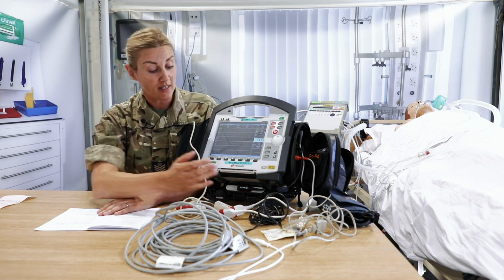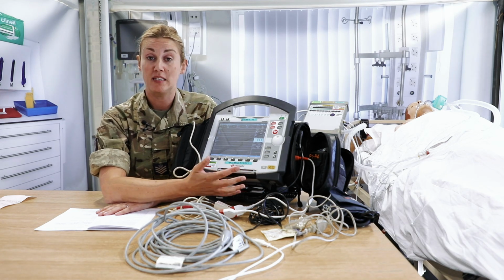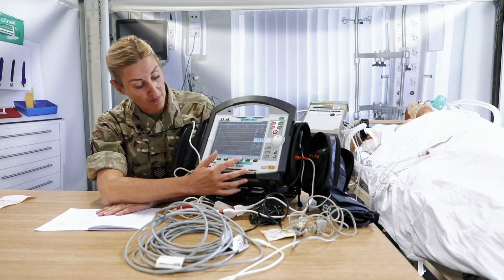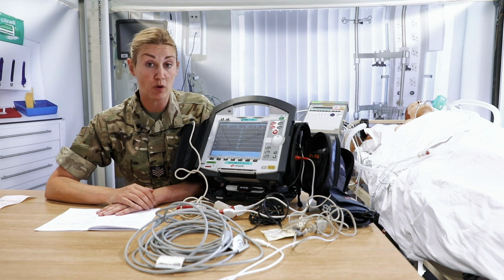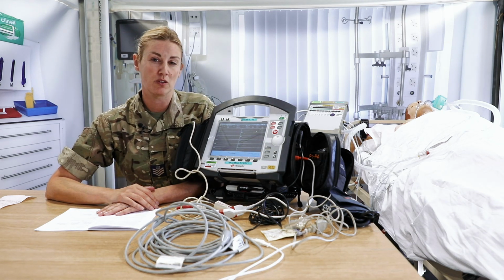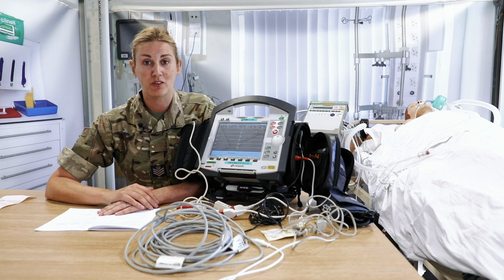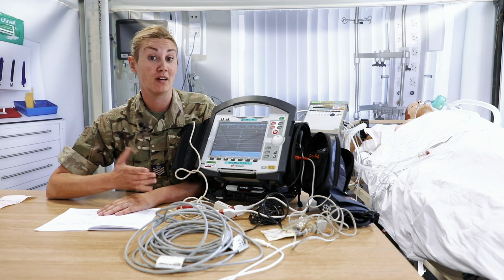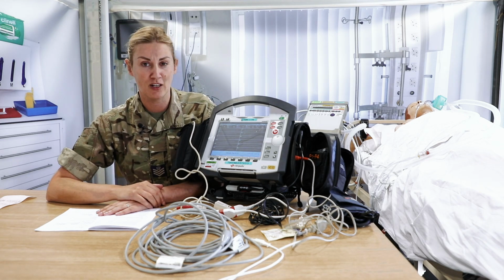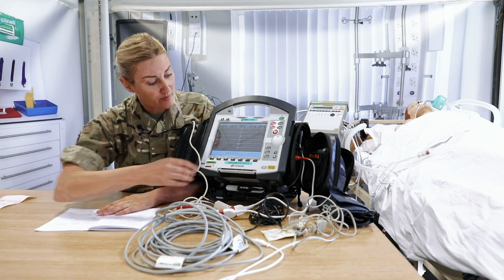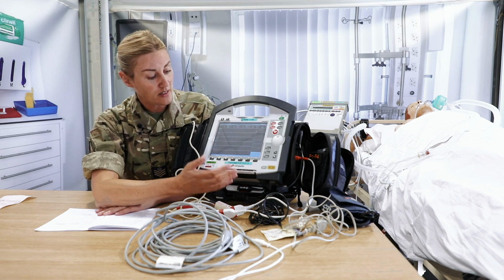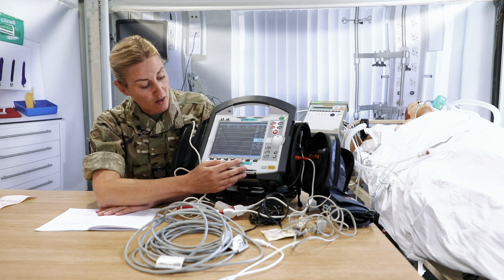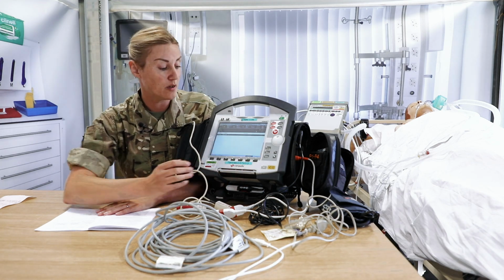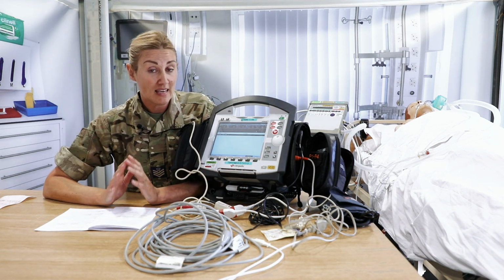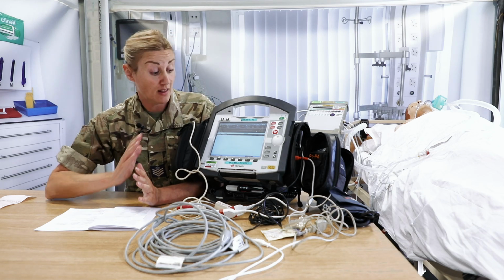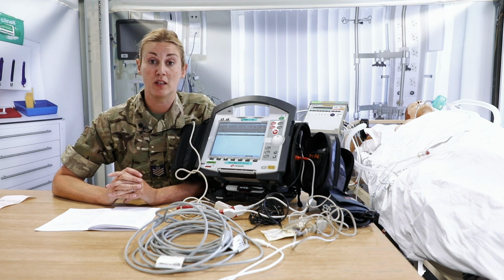So we've checked all of our leads, and we're going to move on to our two ECG functions. So we have an ECG function here, which is our diagnostic ECG. So this is our 12 lead function. All you're going to do is press the button and confirm that a 12 lead ECG appears and that it looks like it should be in the correct order. Cancel that and come back out to our main screen, and our next button is our long-term ECG. Again, all you're going to do is confirm that long-term ECG becomes available and that you can see it.